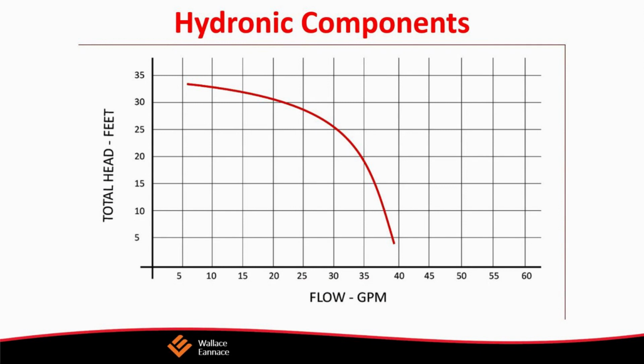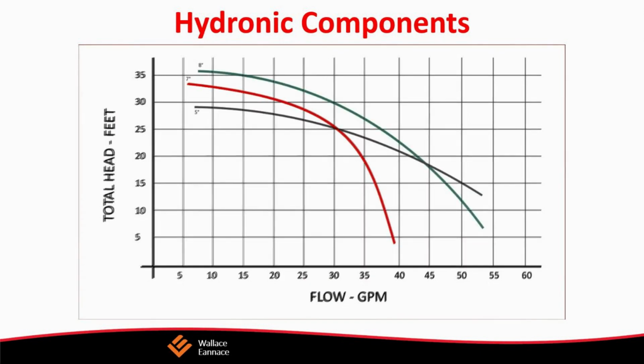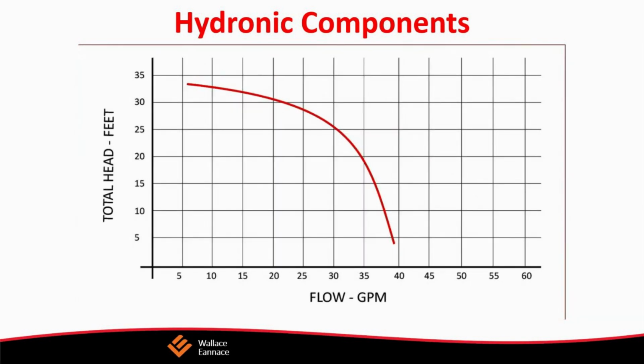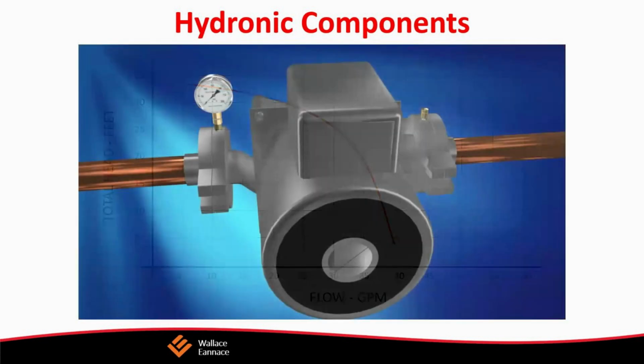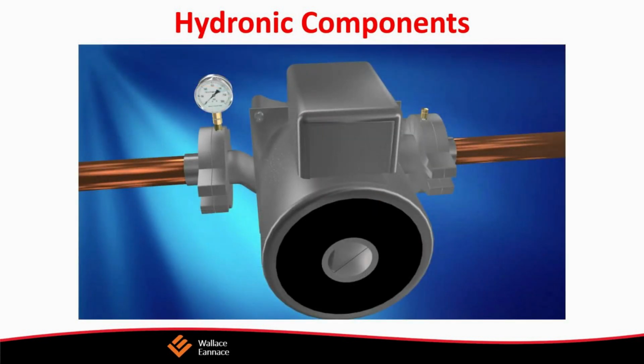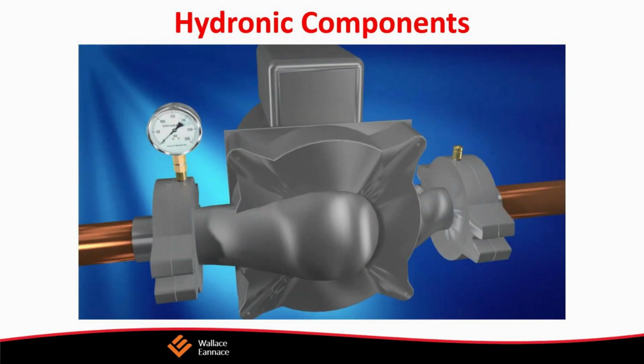Most circulators will have test ports on the suction and outlet sides of the volute. But how do I know the suction from the discharge side? There's actually a very simple method. If you look at the bottom of the volute, you'll notice that one of the sides of the circulator is piped directly to the center of the body. This is always the suction side of the circulator. We know this because the impeller that is housed inside the volute begins to spin, and it creates a Venturi effect. You could imagine this as a mini hurricane inside the body of the circulator.